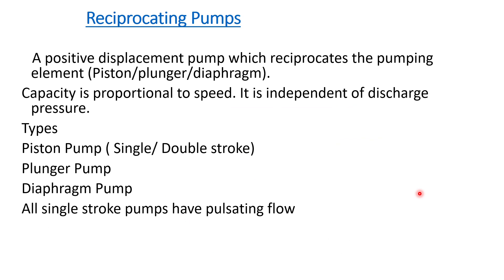A reciprocating pump is a positive displacement pump which reciprocates the pumping element that moves in a linear motion. This pumping element may be a piston, a plunger, or a diaphragm. The capacity is proportional to the speed and is independent of the discharge pressure — meaning the capacity is always the same whatever the discharge pressure is, which is why it is called a positive displacement pump.